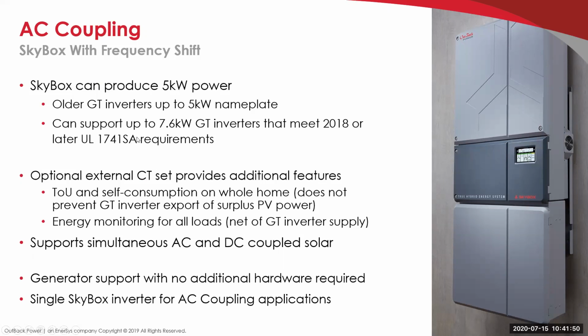So if it's something that's come out in the last few years, then if Skybox starts putting power above this 5 kW, it'll use that frequency watt function of California Rule 21 or HECO Rule 14. I think the California Rule 21 62 hertz version works the best from the testing I've done. So even if you are not in California, you can still put the grid-dependent inverter in that mode, so it will respond to the frequency watt function. And you'll need to check with your local utility to make sure they're cool with that, but I can't imagine why they wouldn't be.